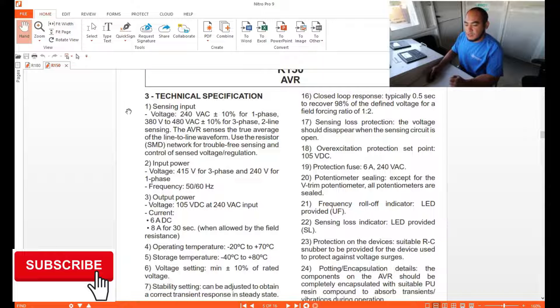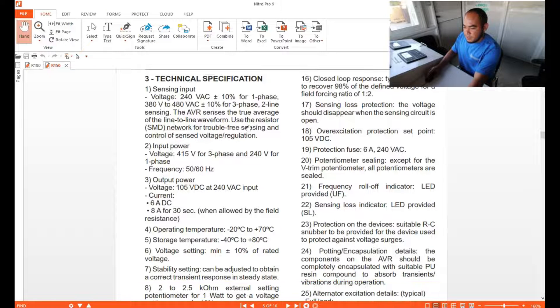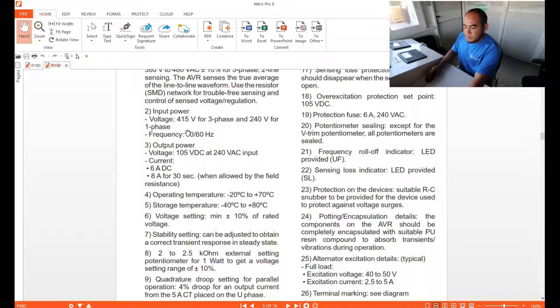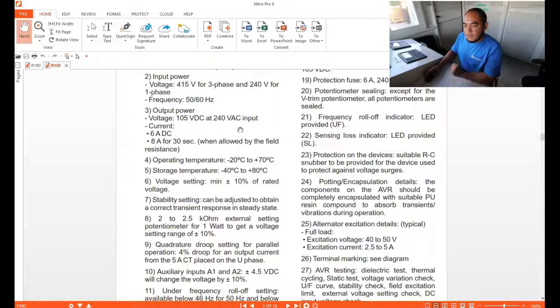The technical specifications: the sensing input is 240 V AC ±10% for single phase, and 380 V to 480 V AC for three-phase sensing. The input power is 415 V three-phase and 240 V for single phase, applicable for 50 and 60 Hz.